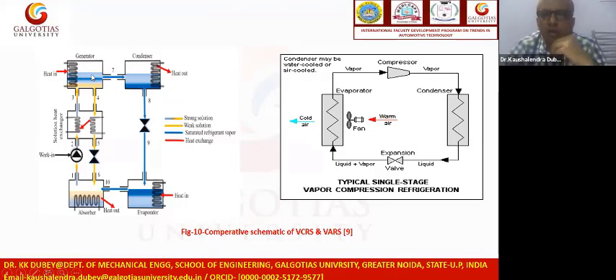Here the hot water, about 80 or 70 degrees, again follows the return track, because the weak solution, the water, has some temperature, about 60 to 70 degrees C. So we can use this thermal energy for the reheating of the solution. That's why we are using the heat exchanger here. Then the water comes again to the absorber, and this cycle goes on for the cooling effect.